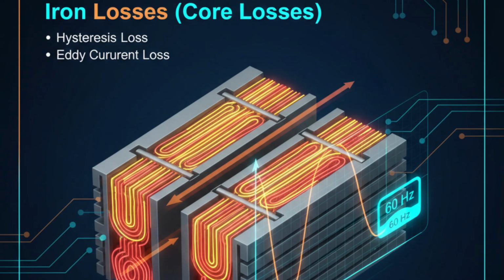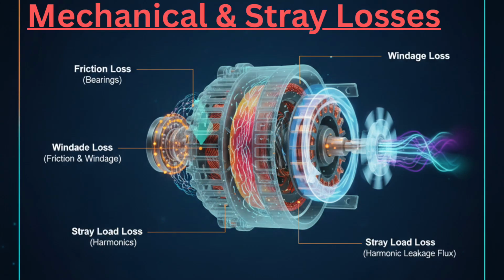Hysteresis loss depends on the magnetic properties of the steel, while eddy current loss results from circulating currents induced within the core. These losses increase with frequency and magnetic flux density, which is why operating generators above rated voltage or frequency is dangerous. Iron losses are almost constant for a given voltage and frequency, even when the generator is lightly loaded. Engineers reduce iron losses by using thin laminated silicon steel cores, which interrupt eddy current paths and improve overall efficiency. Mechanical or stray losses.